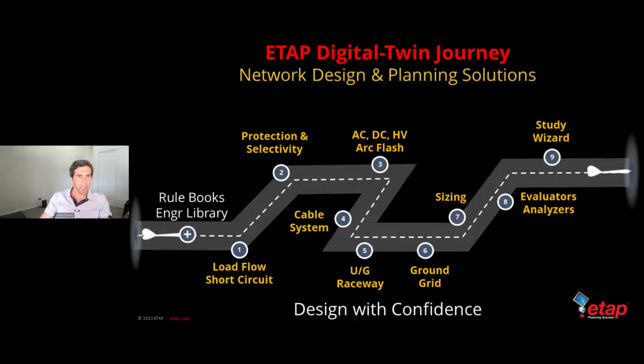Now, for the digital twin journey, I'll show the software soon. We'll look at rulebooks and the engineering library, which form the base of our analysis model, then look at running load flow, short circuit, protection and selectivity, and arc flash—including AC arc flash, DC arc flash, and high voltage. This covers three-phase and single-phase AC up to 15 kV per IEEE 1584-2018, along with various standards for DC and high voltage arc flash above 15 kV, and OSHA-compliant standards as well.